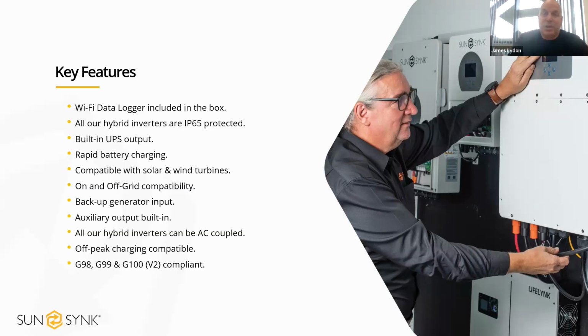And what gives us the USP on the wind is built into the software on the inverters. We have what's called a 12-point power curve. If you imagine the PMG, the permanent magnet generator on a wind turbine, it works similar to a bicycle gear mechanism. If you're in first gear, it'll spin really freely when there's not much wind. But as the wind speed picks up, the turbine will spin faster, and as it spins faster, the voltage that the permanent magnet generator outputs increases.